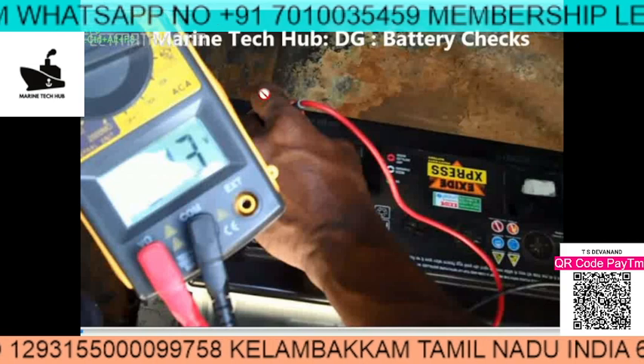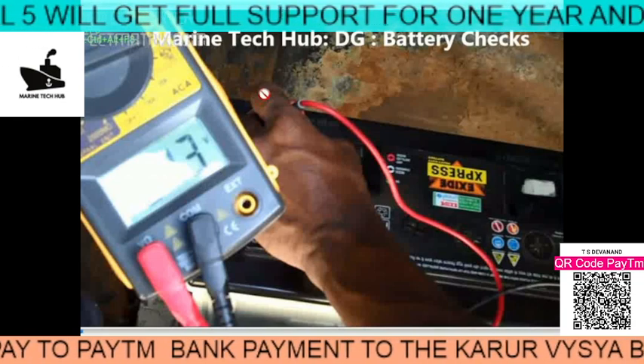If you have an HRD meter — a High Rate Discharge meter — on board the ship, that is very good and you can do the load test with that meter. If you don't have one, you can order it; all ships should have an HRD meter. Otherwise, you have to do a real load test by starting the generator or the lifeboat, keep the multimeter on DC, and you will see the voltage drop while starting. That voltage drop is the important thing to observe.